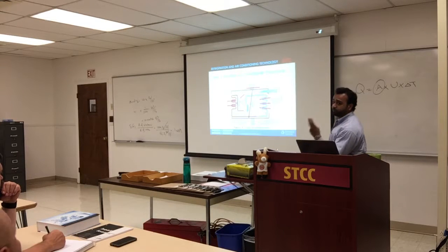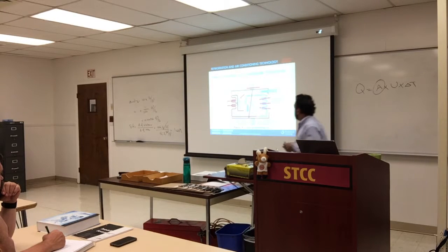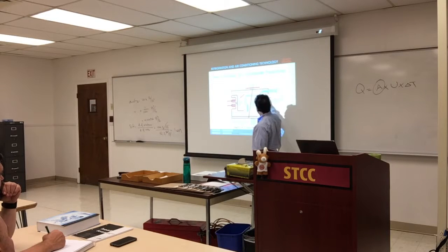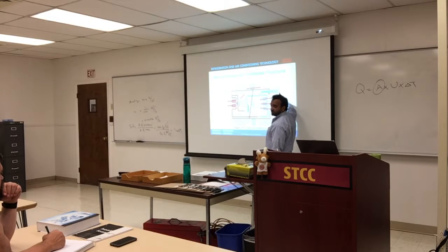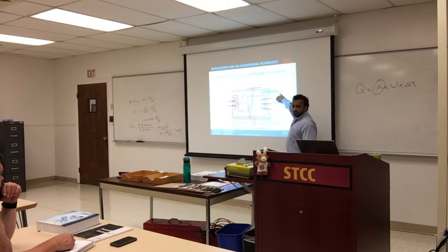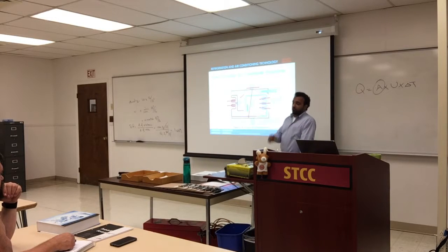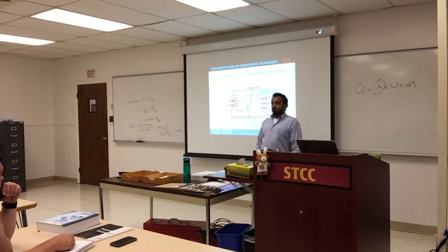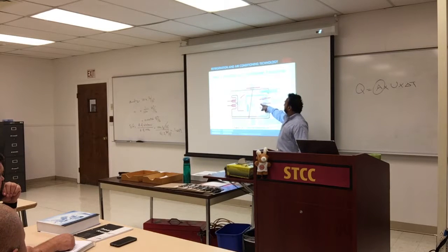So what is the fluid here? There are two fluids working. One of them is the outside, which is the air, and the inside is the refrigerant. The refrigerant is circulating continuously through the fins over here. So what is the temperature difference? The room is 75, there's 20 degrees difference here. That's very good heat exchange. That's a good rate. And if you ever notice that if you run the fan too high, the room might not cool as fast, because you're not giving the air enough time to exchange heat with the coil. It's going too fast. So you circulate the air through the fan with the right speed over the coils.